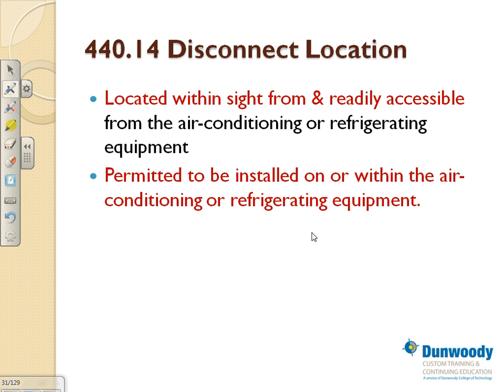The disconnect for the equipment, guys, must be within sight. Within sight is defined by the code as not further than 50 feet and no obstacles. So it could be 50 feet and I have to jump 20 feet to reach it. That's an obstacle, right? It has to be straightforward, no climbing over, under, or in between, and not further than 50 feet, readily accessible from the air conditioning or refrigeration equipment. You can put it on or within the air conditioning or refrigeration equipment. So with a chiller, you can put the disconnect right on the chiller. And in 2008 they came up with a rule: if you have a disconnect right on the chiller, don't mount the disconnect on the nameplate of the chiller or compressor.